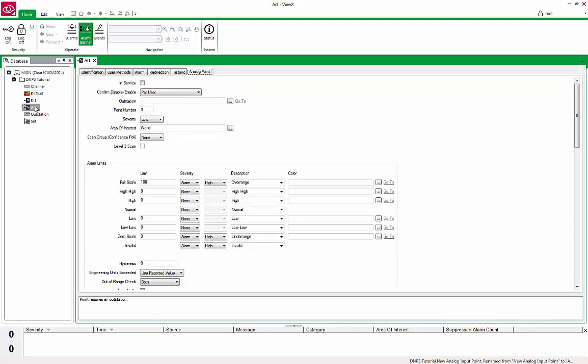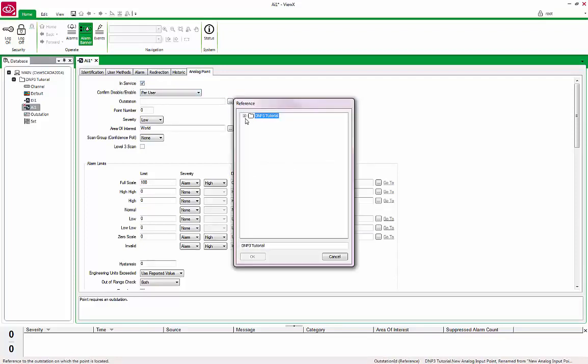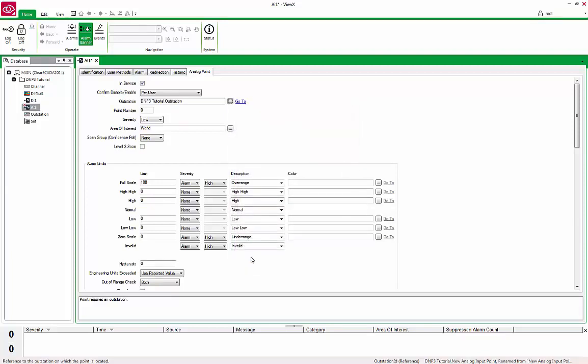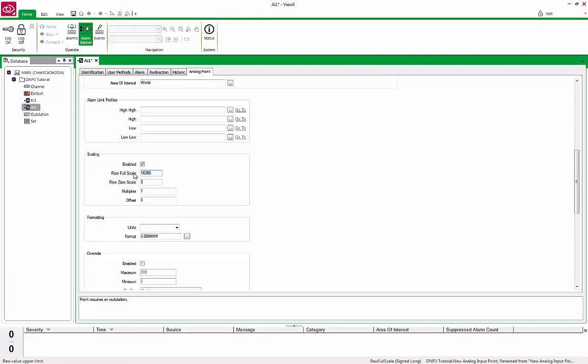Under the Analog Point tab, check the In Service button. Tie the point to the Outstation by browsing to the Outstation we defined earlier. Set the Point Number to 1, which is the first analog point in our device. Scroll down the Configuration page to Scaling and set the Raw Full Scale. This is the max value provided by the sensor attached to the analog input of the device which is translated to a max value of 100. Your device value may not need to be scaled, and as such, you can uncheck the Enabled box.